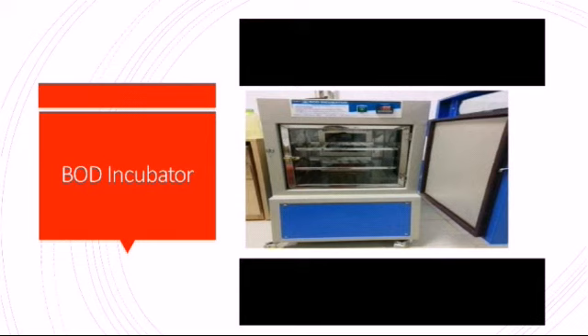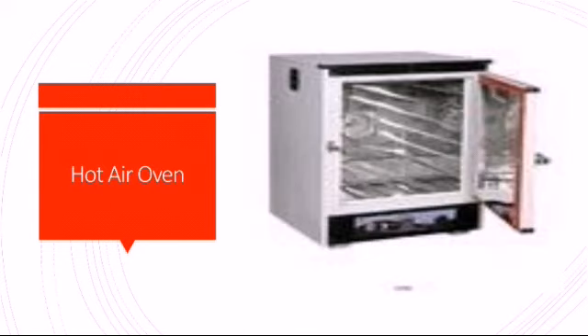Hot air oven. Hot air ovens are electrical devices which use dry heat to sterilize. They were originally developed by Pasteur. Generally, they use a thermostat to control the temperature. Their double-walled insulation keeps the heat in and conserves energy, the inner layer being a poor conductor and the outer layer being metallic. There is also an air-filled space in between to aid insulation. An air circulating fan helps in uniform distribution of the heat.